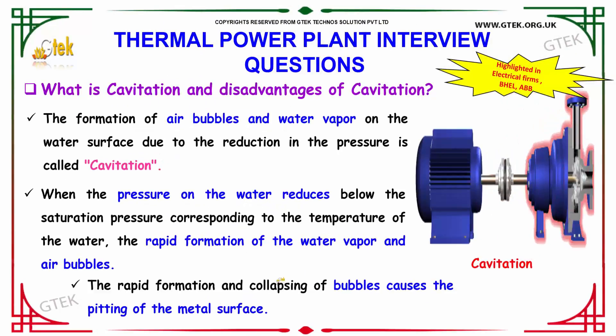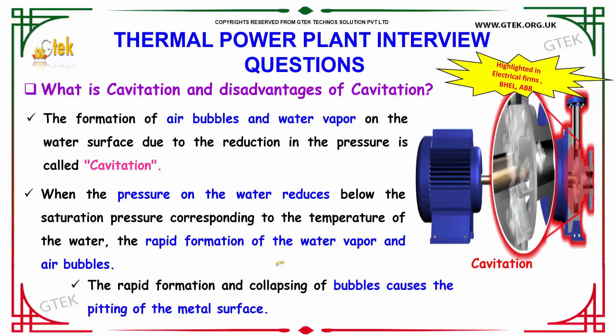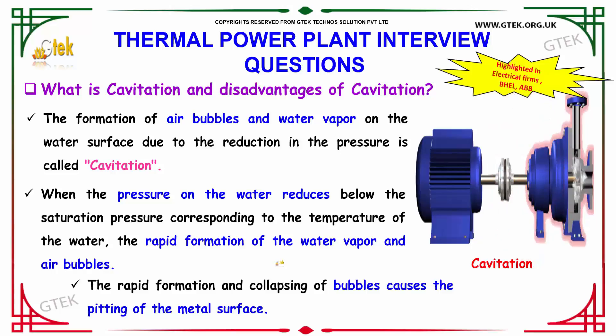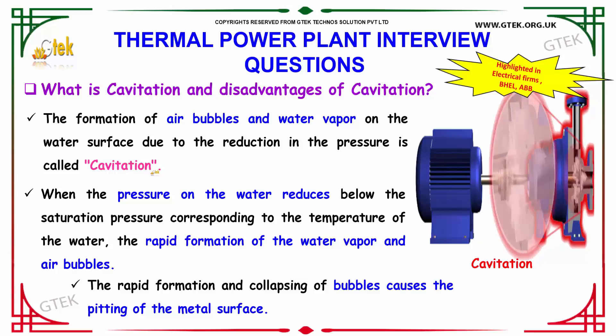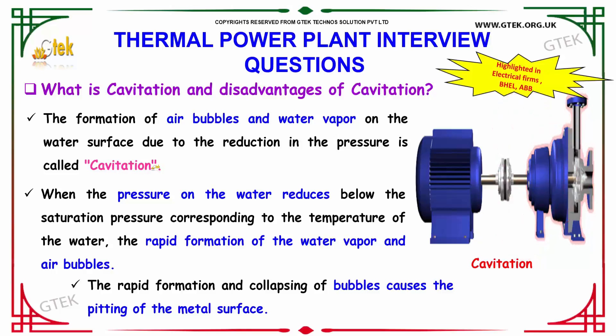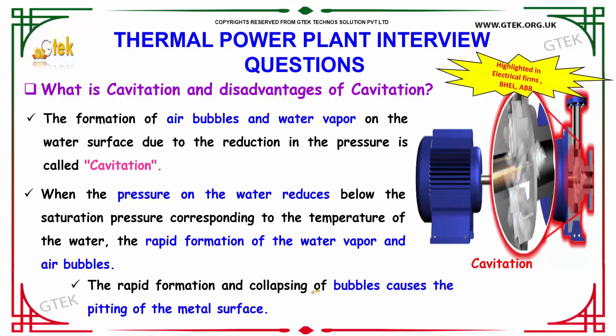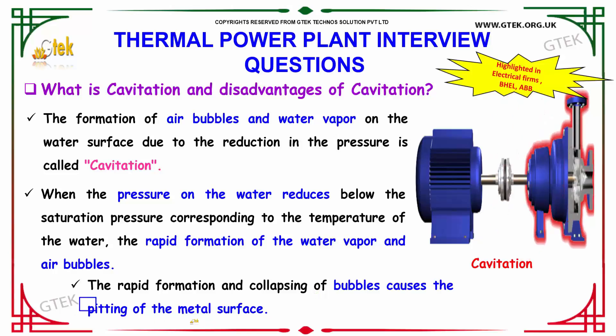What is cavitation and what are its disadvantages? The formation of air bubbles and water vapor on the water surface due to a reduction in pressure is called cavitation. When the pressure on the water reduces below the saturation pressure corresponding to the temperature of the water, rapid formation of water vapor and air bubbles occurs. The rapid formation and collapsing of bubbles causes pitting of the metal surface, which is the disadvantage of cavitation.